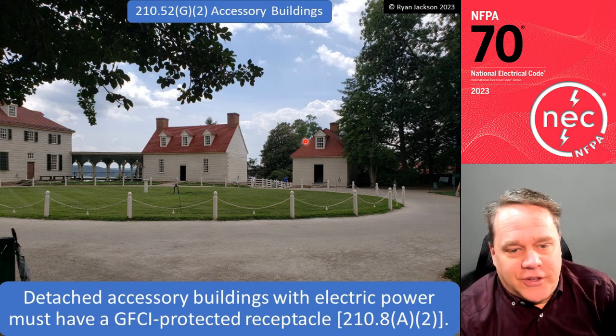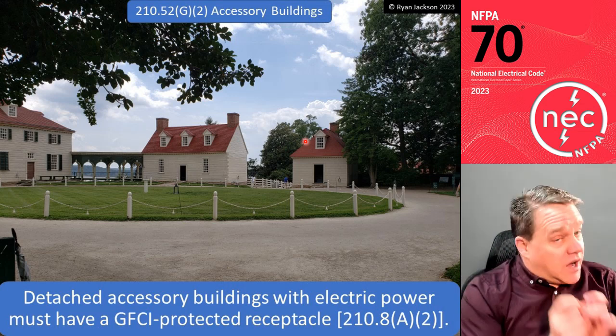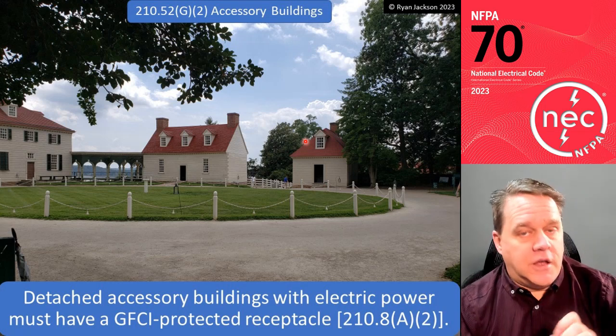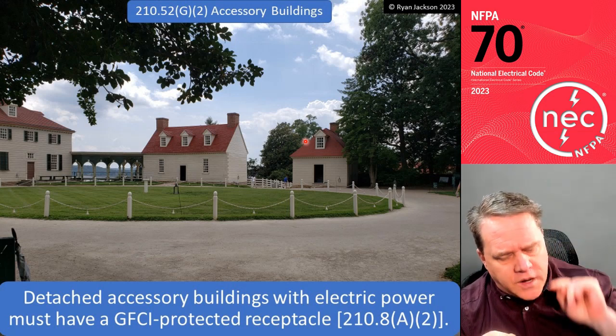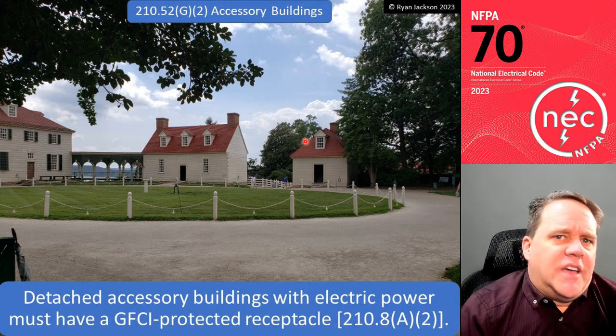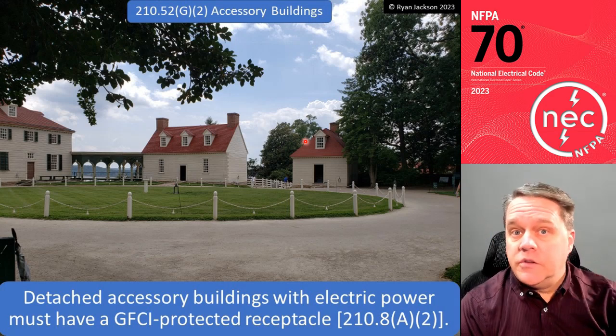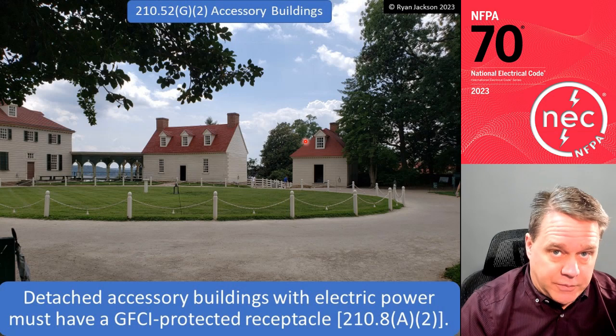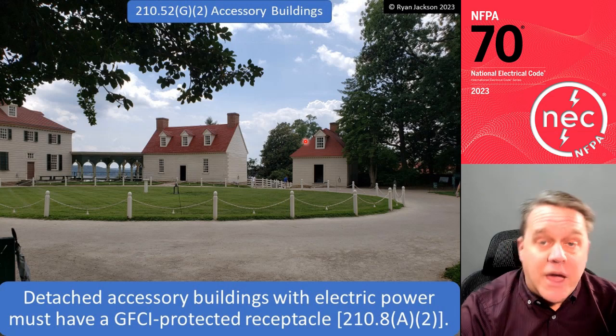Detached accessory buildings with electric power must have a GFCI protected receptacle. All right, we're not going to make you run electricity to your detached building, okay? But if you do, then you need to have a receptacle out there. And that makes sense because if you're running electricity out to your garage, out to your detached building, and you're not installing a receptacle, what are you installing? A light, probably, right? So you've got a light out there but no receptacle. It's a tool shed, right? I don't need any receptacles. Well, what happens when you replace your lawnmower with a battery-powered lawnmower?